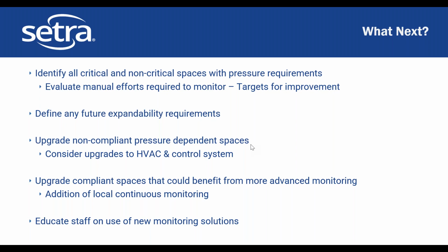The best practice for the facility, for the outcome of patient care, is to make sure that we're monitoring and we know that all our spaces are in spec all the time. Doing the weekly, the monthly, the yearly balance, we cannot guarantee that all year that was actually the case. That is not the best practice. So additional local monitoring, and again, we talked about that you may actually have some labor savings in these instances. Your team, your nursing staff, even your facilities team, their time is better spent taking care of other things than walking around and making sure that your linen closet is properly pressurized.